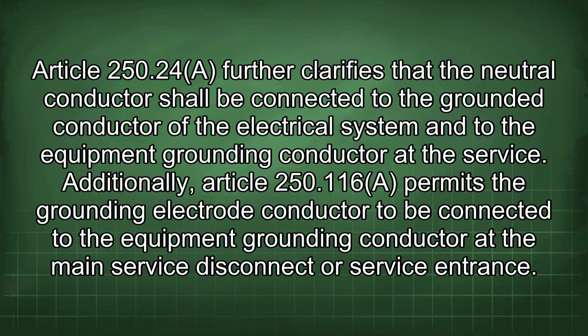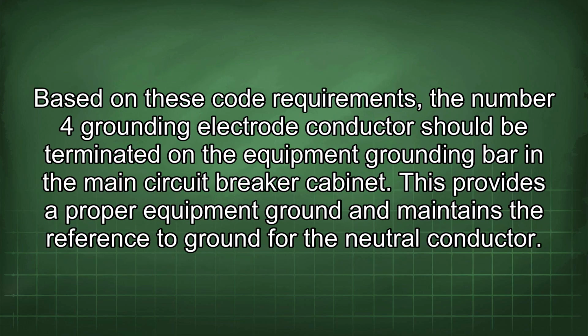Additionally, Article 250.116 permits the grounding electrode conductor to be connected to the equipment grounding conductor at the main service disconnect or service entrance. Based on these code requirements, the number 4 grounding electrode conductor should be terminated on the equipment grounding bar in the main circuit breaker cabinet. This provides a proper equipment ground and maintains the reference to ground for the neutral conductor.